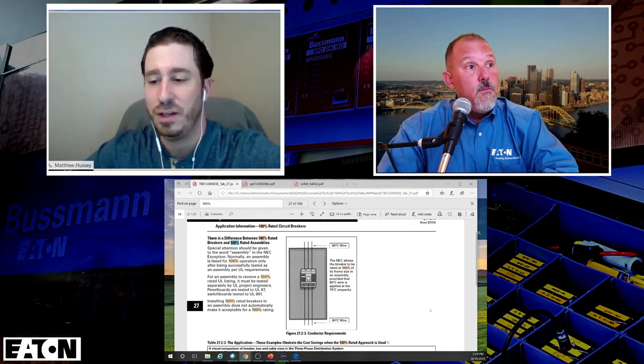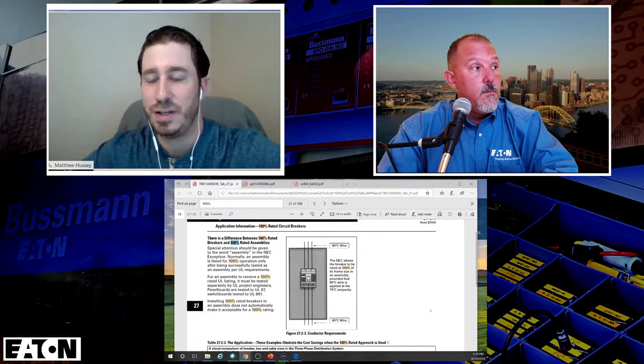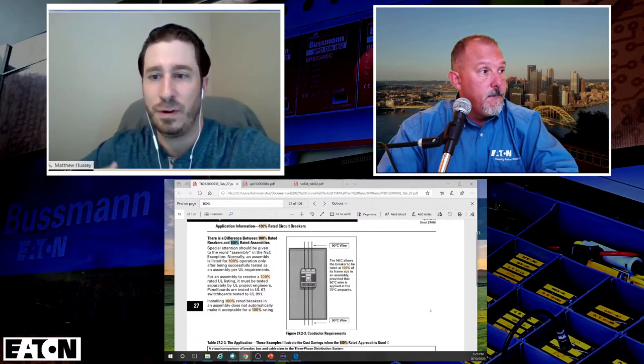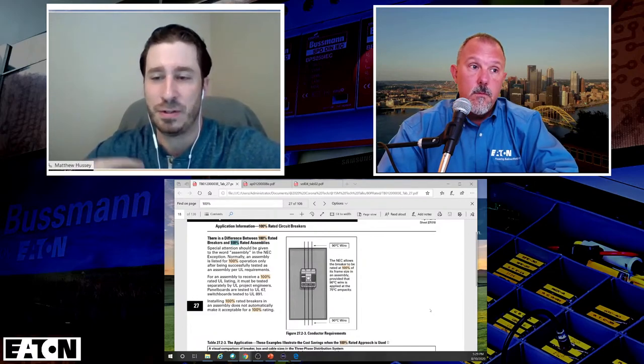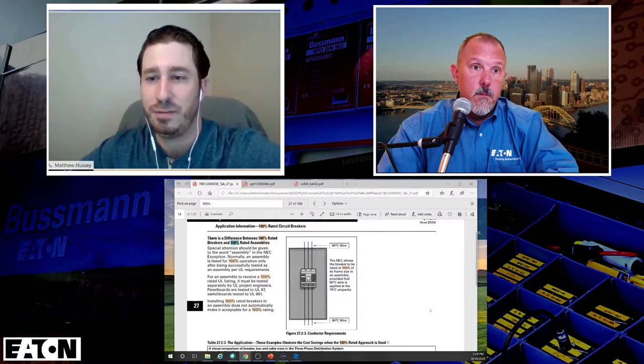Yep. It goes back to when those devices were originally tested and rated for current, they were all calibrated and dependent upon a certain conductor size downstream of it. So as those things change, we've got to be able to accommodate those changes.